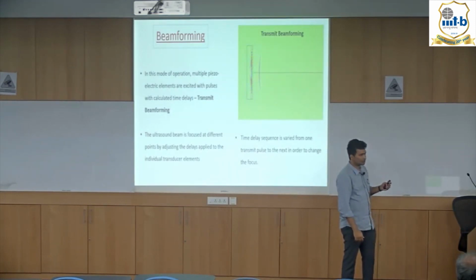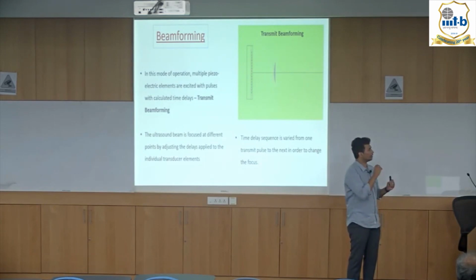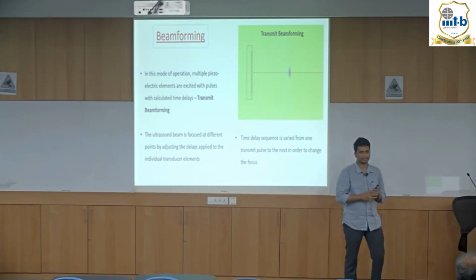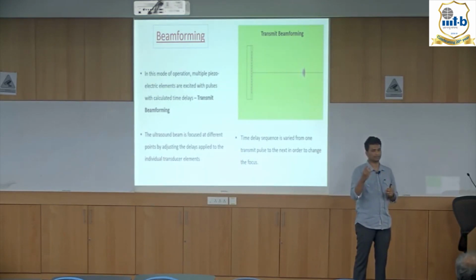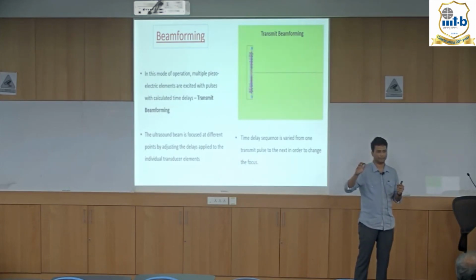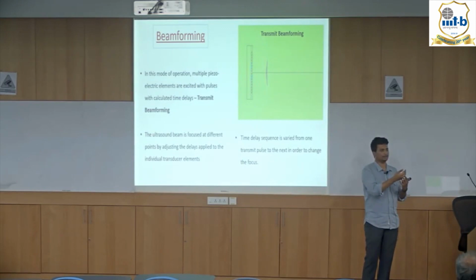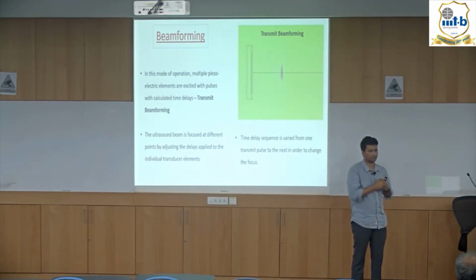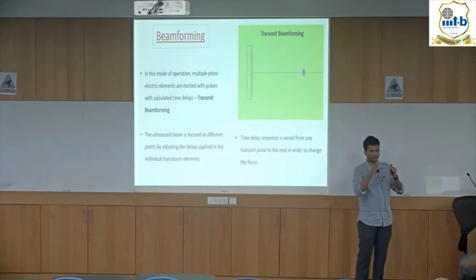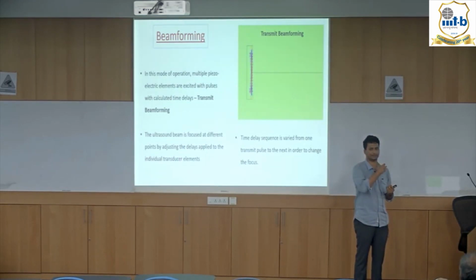There is another concept called beamforming, where the piezoelectric crystals are fired such that there is maximum constructive interference at one of the points in the medium. They calculate the delay values at which each of the piezoelectric crystals should be fired, and once they get fired, they have a constructive interference at one particular point in the medium. Because of this, even with a lower voltage, we can send a strong transmit pulse, so we can get a good echo. You get a specific focus point. In and around the focus, the echo reflected by the medium will be strong.